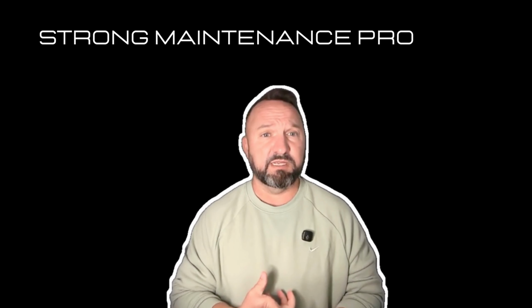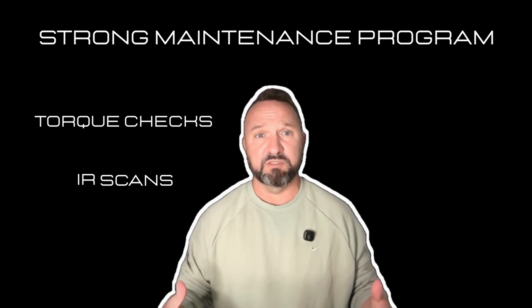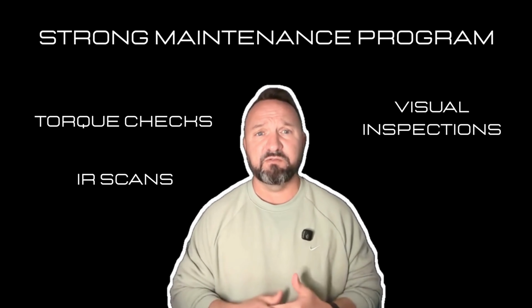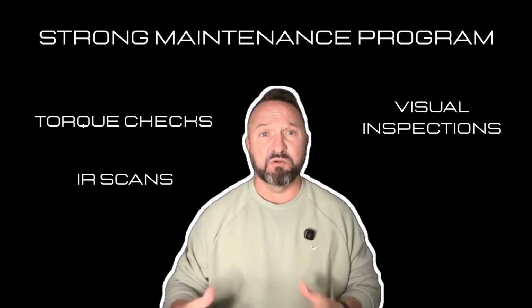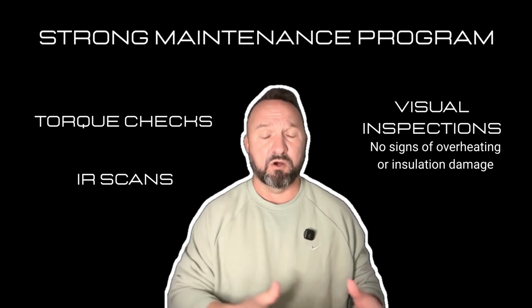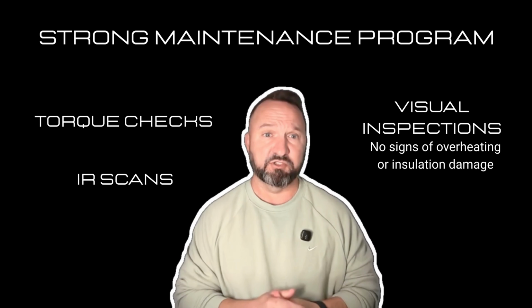Another thing that typically causes failures is loose connections. Loose connections increase resistance and heat and potential arc fault events. Routine inspections include torque verification, infrared or thermal inspections, and just verifying the connectors and there's no signs of overheating, arcing, or issues with our connection points. These steps will prevent premature equipment failures.